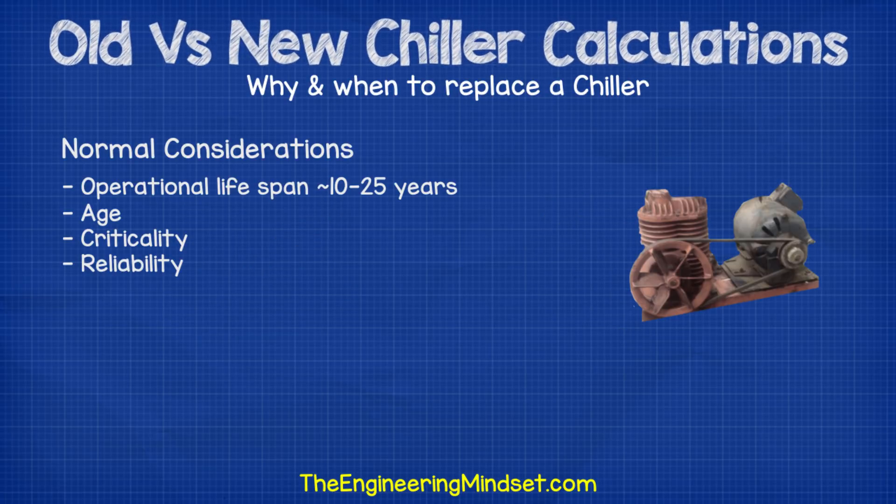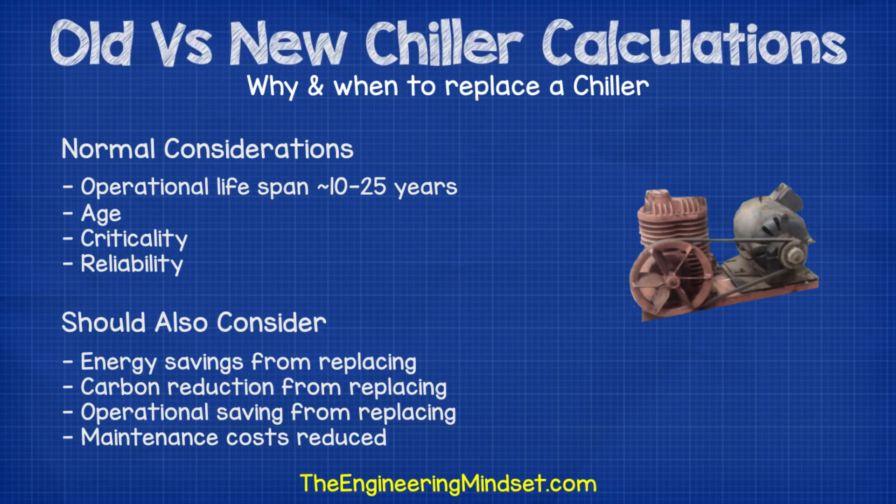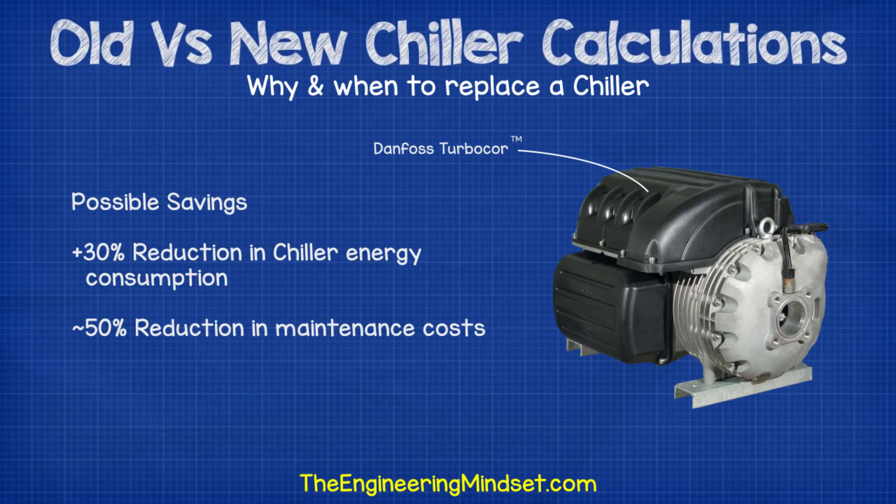Why and when to replace a chiller? Chillers typically have an operating lifespan of 10 to 25 years. Their age, condition, criticality and reliability usually play the biggest part in deciding when to replace a chiller. What should also be considered is the huge energy savings that can be achieved from improved efficiency with newer technology, and also the reduced maintenance costs. For example, replacing an existing chiller with a turbo core chiller can in many cases cut the chiller's annual energy consumption by around 30% — sometimes even higher — and the maintenance costs will be around 50% less because the Turbocor compressor is oil-free, so the only maintenance requirements are to change out the capacitors about once every five years.